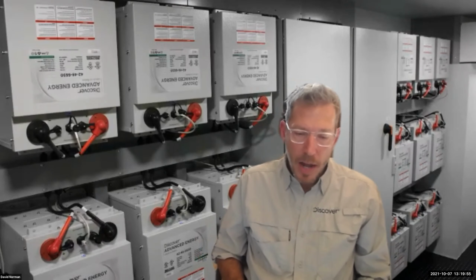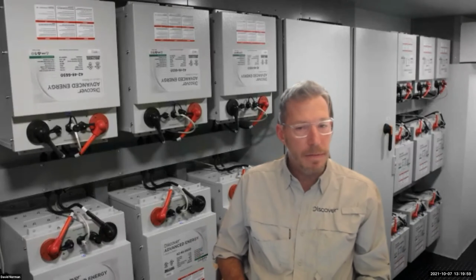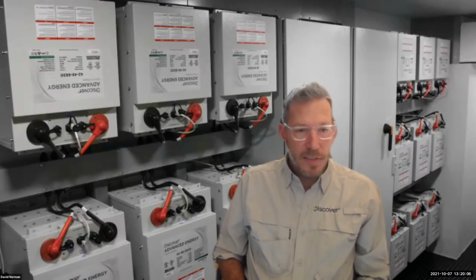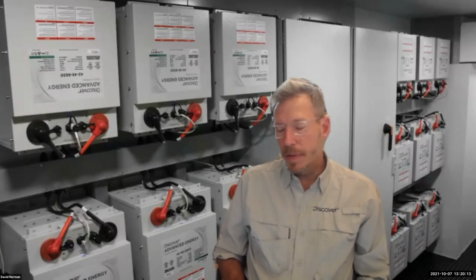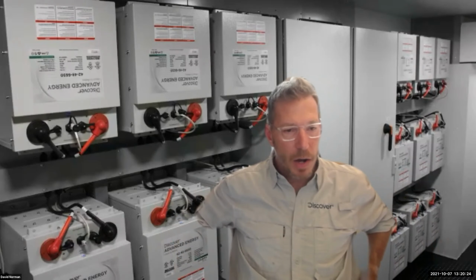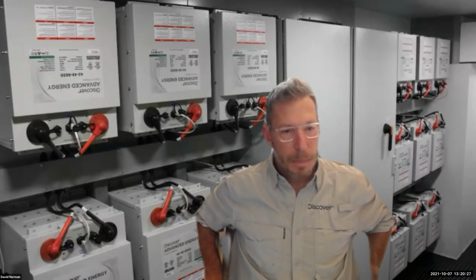But externally, I know a lot of the extreme containerized systems that might be operating for, say, Homeland Security or the DoD, or telemetry stations and things that are remote, typically have some kind of HVAC system, whether that's from heat mats or a compression system, some means of maintaining the temperature within the operating parameters of the devices. Yeah, we used to have heater options for our utility scale inverters when we were in that business. But as far as the XW Pro, the data sheet says minus 13 Fahrenheit all the way up to 158 degrees Fahrenheit is the operating temperature range.